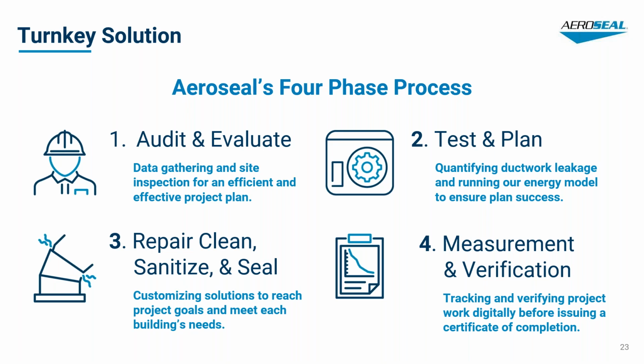So we're going to tell you in that audit process what needs to happen. If it's just duct sealing, that's great. If there's other issues in your building, we will tell you that as well. So if there's bigger holes than 5/8 of an inch, we will let you know that as well. If we think that there's some cleaning that needs to be involved, any sanitization, anything like that, we will let you know that in that audit process, and then we will be able to do that when we're out there as well. And then there's the measurement and verification process. Every time we seal up a section of the duct, you'll get a certificate of completion that has the test information that tells you how much leakage was there when we started, and then it has that verification of how much leakage is there when we're done. So you know exactly how many CFMs we sealed up while we were there.